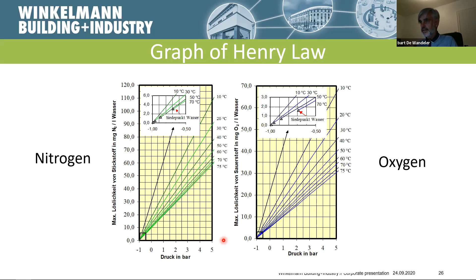Degassing is necessary, but it all starts with the water makeup. When you fill an empty system, a new system, or an old system after repairs, the first thing you use is potable water, which is not degassed at that moment. This is natural behavior, not something invented - it's not untrue. Natural water content has at least a minimum of 11 milligrams of oxygen, and even more nitrogen, around 18 to 20 milligrams per liter of water. So from the start, you're already putting a lot of air, oxygen and nitrogen into your system.